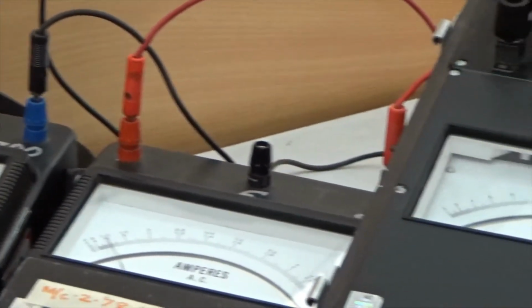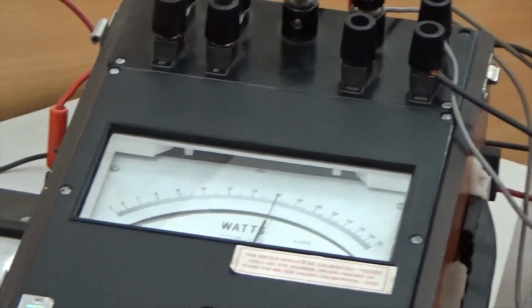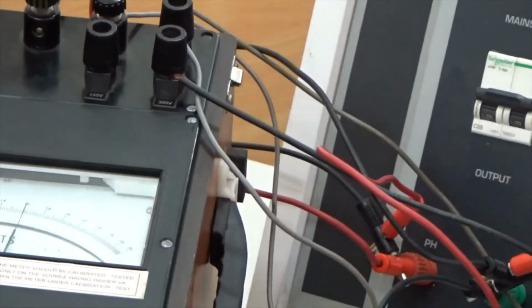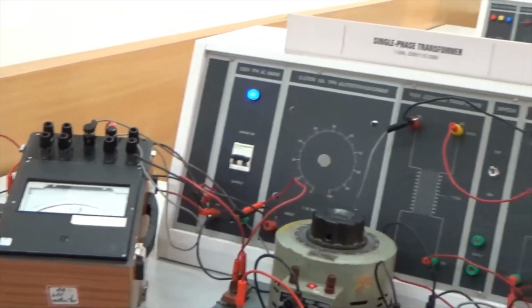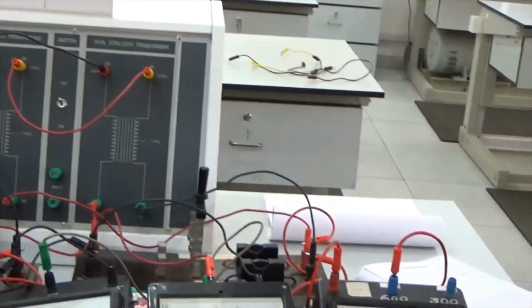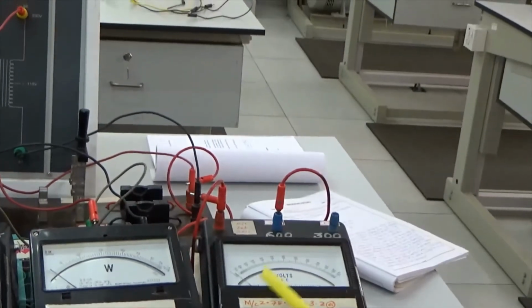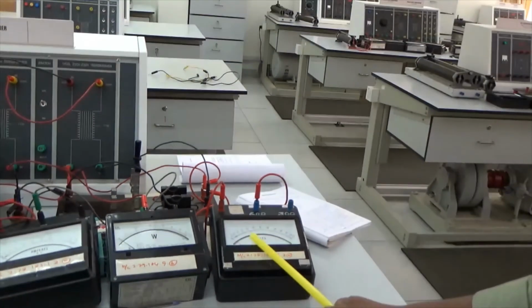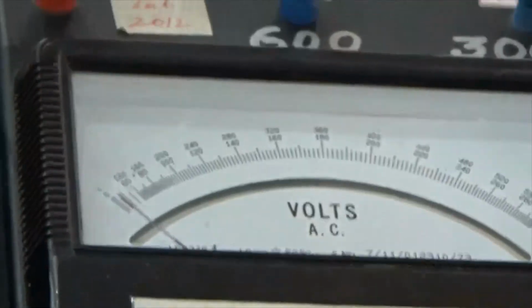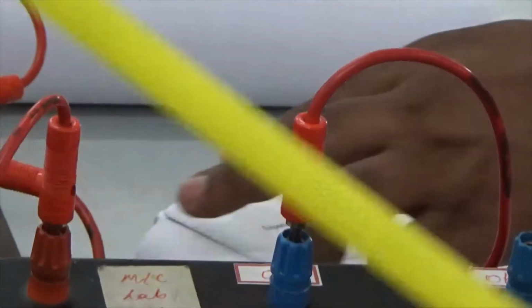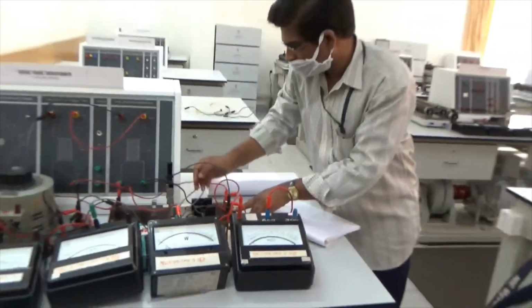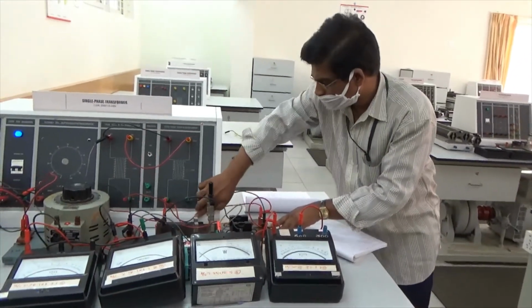So now I will ensure that the secondary phase voltages of the two transformers are in phase with each other, so that the voltage across this switch is zero. Then the switch is ready for the connection to the secondary circuit. Now you switch on that supply, after ensuring it is zero, with the variac kept at the zero minimum position.